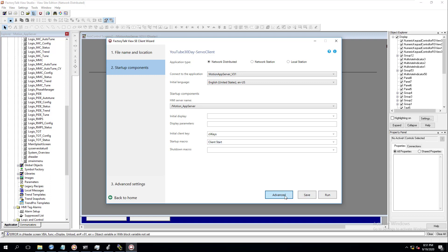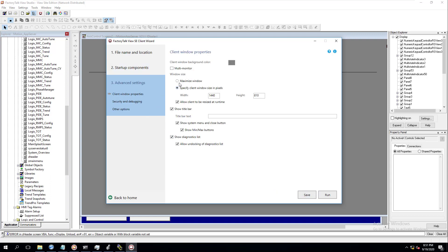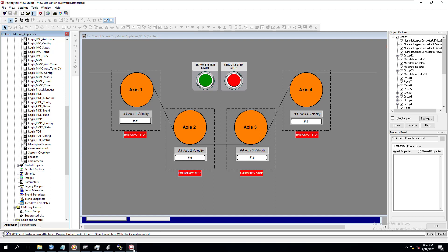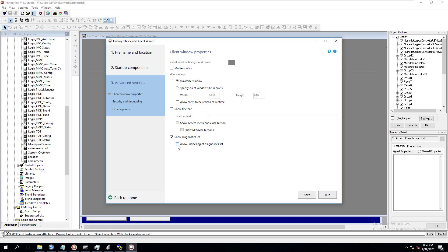At this point I want to get to the Advanced settings. I want to go maximum screen — I don't want specific dimensions. I'm not going to use show title bar, and I'm going to not allow resize. I do want diagnostics — that's normally something you might not want. The diagnostics is the diagnostic bar down at the bottom. If you want diagnostics on your client you can enable that right here. You can also enable allow docking and undocking.